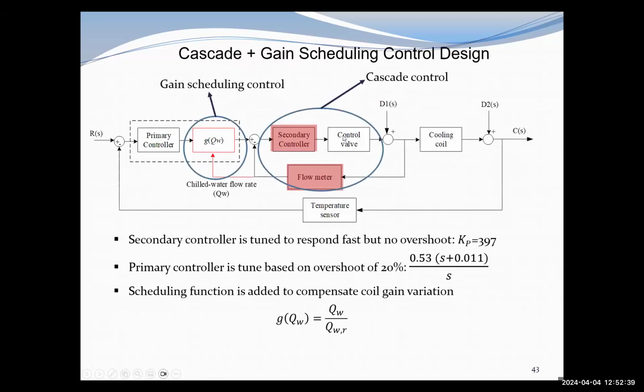Gain scheduling is to handle the cooling coil gain variation, and the cascade is to handle the control valve nonlinearities. Then we think that by combining these two, we are able to compensate both the control valve and the cooling coil nonlinearities. And this is the cascade plus gain scheduling control design, with each controller handling the corresponding nonlinearities.